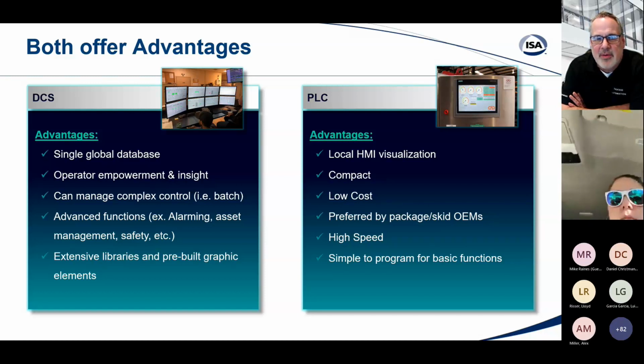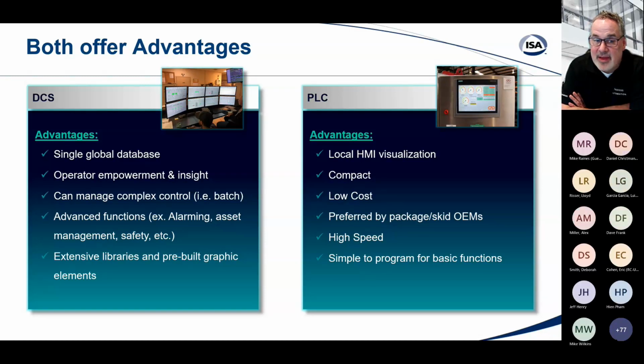As far as advantages of PLCs, the nice thing is they handle a very low-cost local HMI visualization. And I can tell you on the DCS side, we can have a local HMI, but it's not going to be cheap and it's not going to be easy. They're just not built that way. Normally, because that little local HMI doesn't really talk to 2 different PLCs, it's a very simplex communication. So you've got to engineer a solution around that. We've done it before, but it's not easy. So the advantage for the PLC is a local HMI. It's typically more compact, low cost.